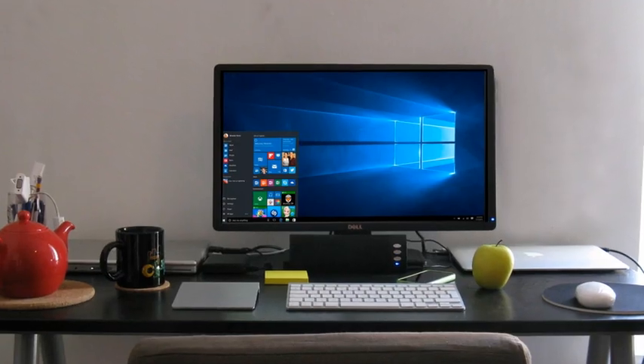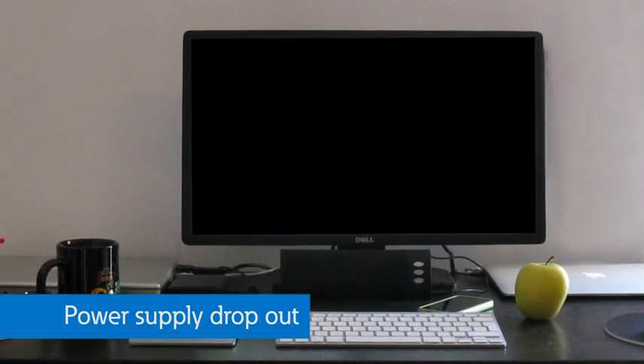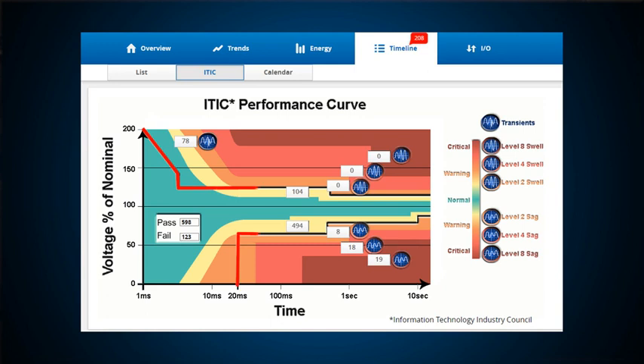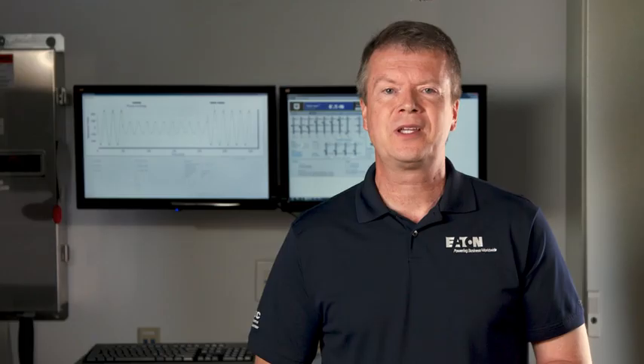These triggers and recordings indicate excessive voltage drop or rise outside those heavy black lines. Consider the relationship between voltage and time. A power supply's ability to ride through a low voltage event is affected by not only how low the voltage dropped, but also how long the voltage dropped. In fact, many if not most power supplies can maintain full output even if the input voltage drops to zero, as long as the voltage returns to a sufficiently high value quickly enough. This complex relationship between voltage drop — also known as retained voltage — and time makes interpreting data, especially waveform data, difficult, but not with the Power Xpert meters.